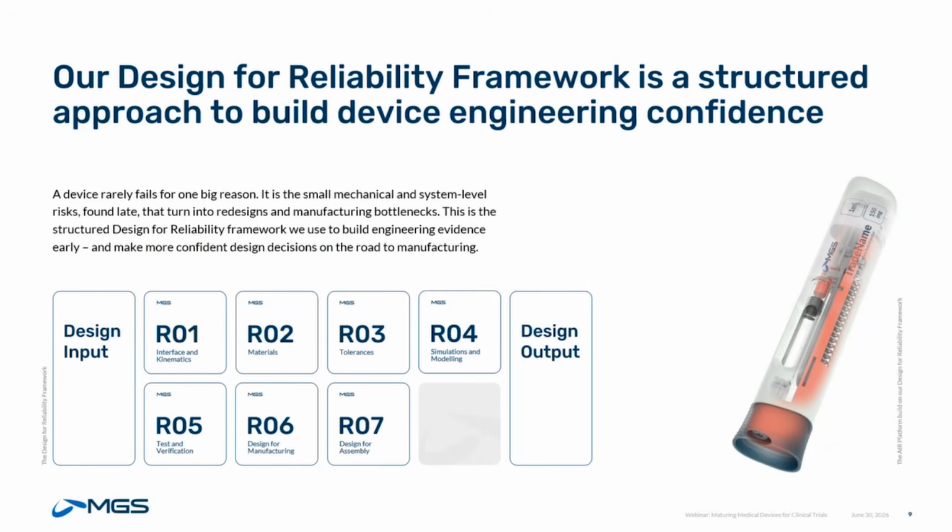Yeah, and I'll go back to the design for reliability framework again to see if we can sort of close the loop. So will a framework like this answer the opening question about when a device is mature enough to go into clinical trial? I'll say from a mechanical engineering perspective, that's when you can make a traceable argument from a potential failure mode and then show the parameters that control it, and also the analysis behind.